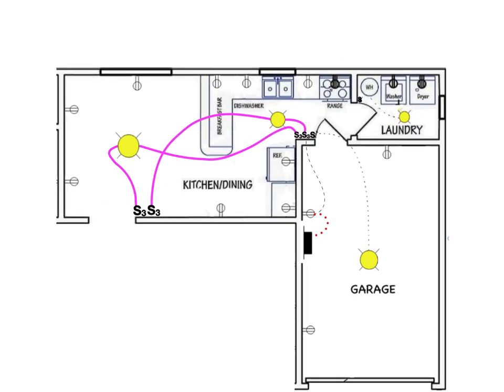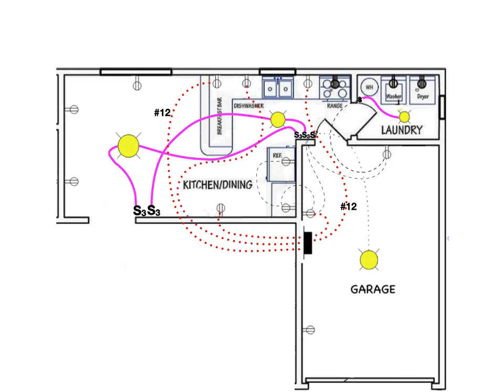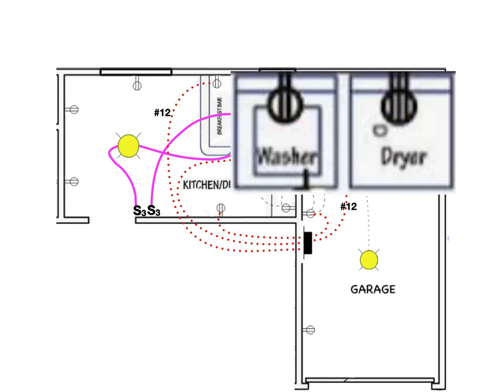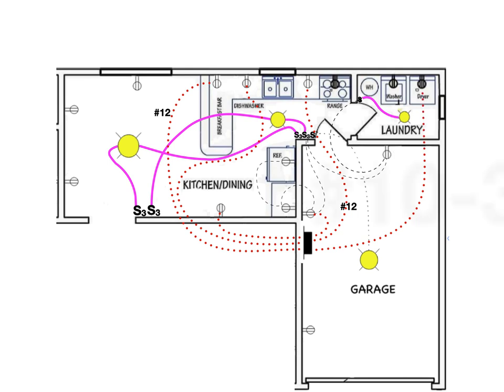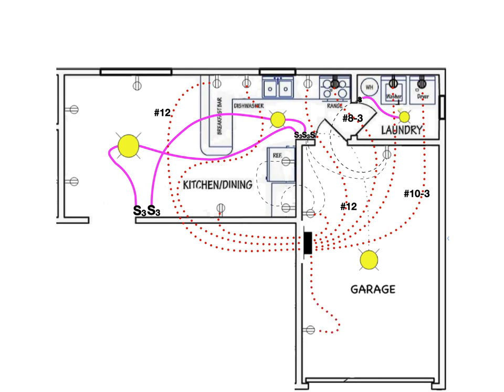Now that we have the three-way lights figured out, let's complete this circuit by picking up the last outlet in the dining room area and the refrigerator circuit. Bringing the feed from that circuit over to the innermost receptacle in the garage, and then continuing on to feed the switch which ultimately lights the laundry room area. The next two feeder circuits will be brought out on number 12-2 wire, fused with a 20-amp AFCI breaker (arc fault circuit interrupter). The dishwasher is going to be fed with a number 14-2 cable and a separate 15-amp standard breaker. The dryer load will require a number 10-3 feeder cable and a 30-amp double pole breaker. The washer will only require a number 14-2 feeder cable and a 15-amp single pole breaker. The range load will require a number 8-3 feeder cable and a 40-amp double pole breaker. Finally, the last outlet plug in the garage will be fed from a separate breaker rated at 15-amp.